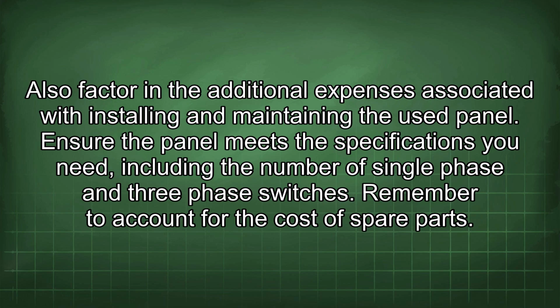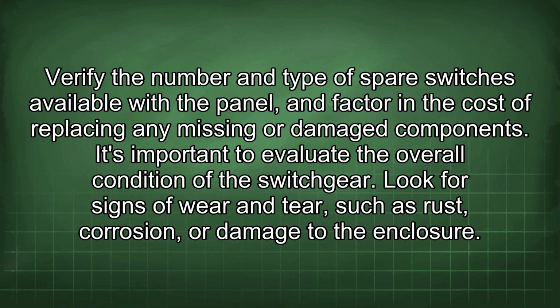Ensure the panel meets the specifications you need, including the number of single-phase and three-phase switches. Remember to account for the cost of spare parts. Verify the number and type of spare switches available with the panel, and factor in the cost of replacing any missing or damaged components. It's important to evaluate the overall condition of the switchgear.